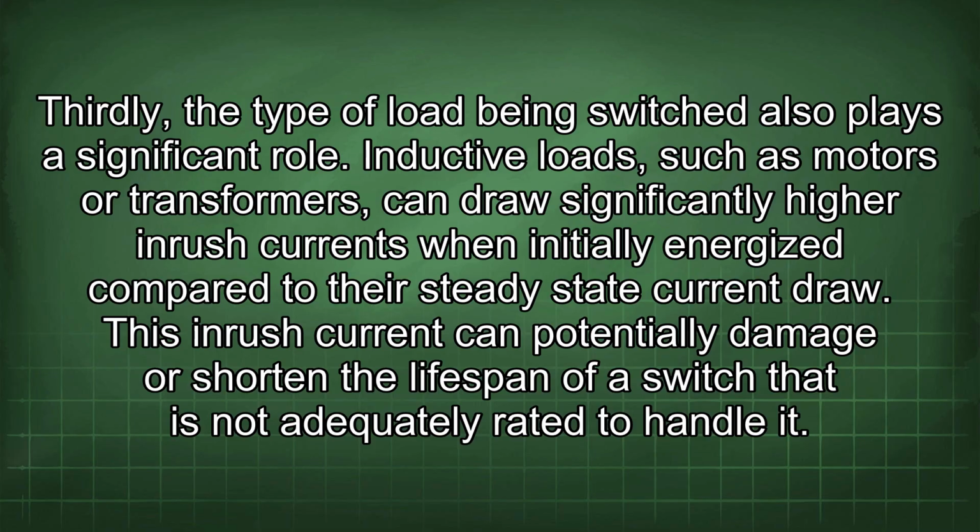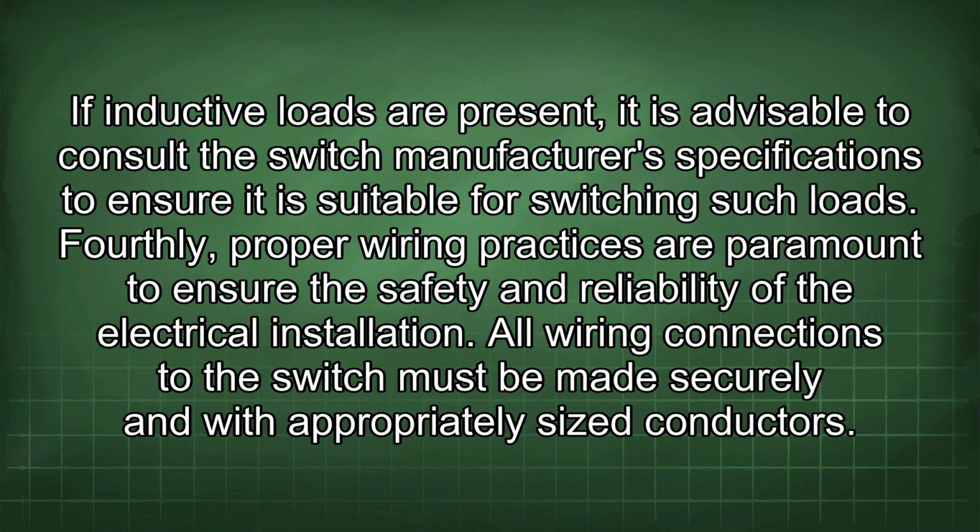Thirdly, the type of load being switched also plays a significant role. Inductive loads, such as motors or transformers, can draw significantly higher inrush currents when initially energized compared to the steady-state current draw. This inrush current can potentially damage or shorten the lifespan of a switch that is not adequately rated to handle it. If inductive loads are present, it is advisable to consult the switch manufacturer's specifications to ensure it is suitable for switching such loads.